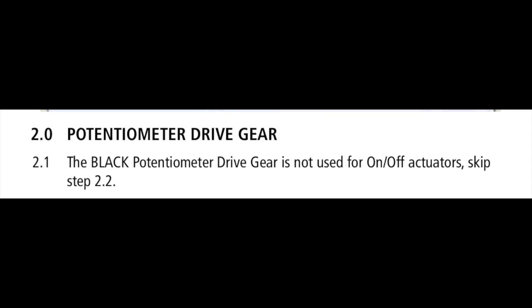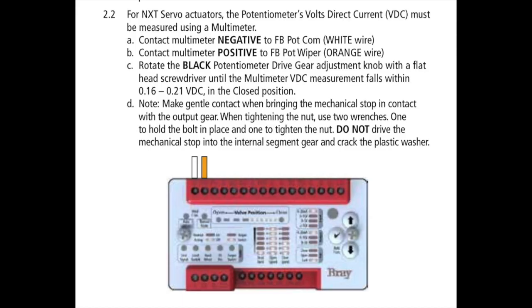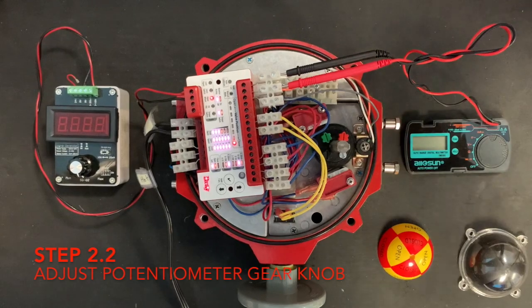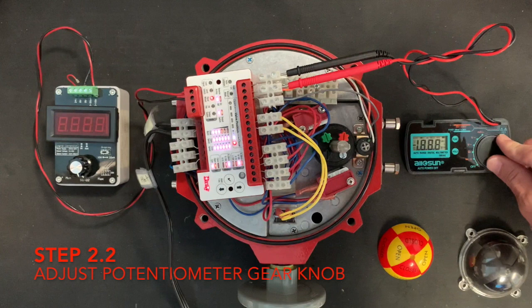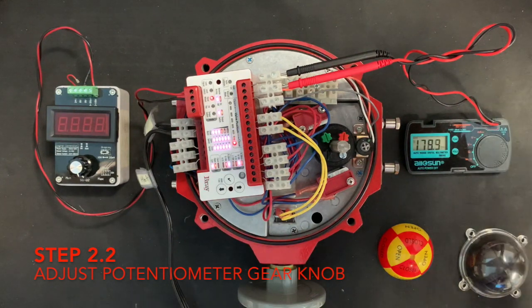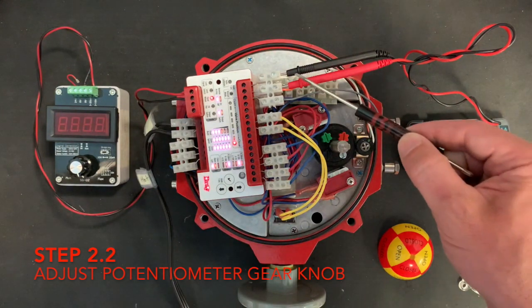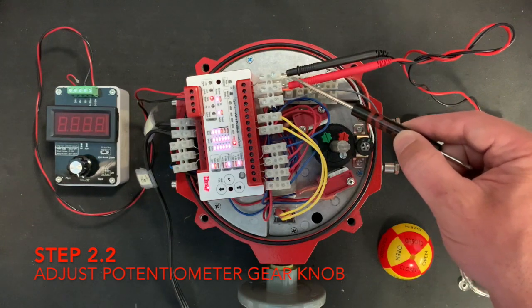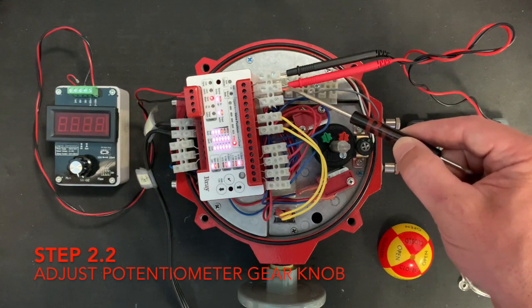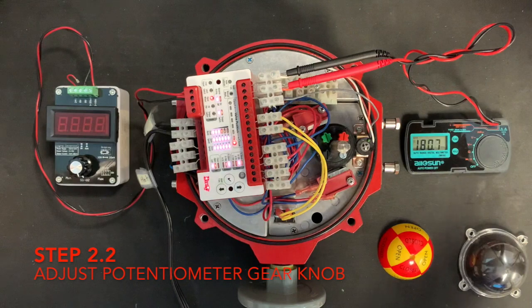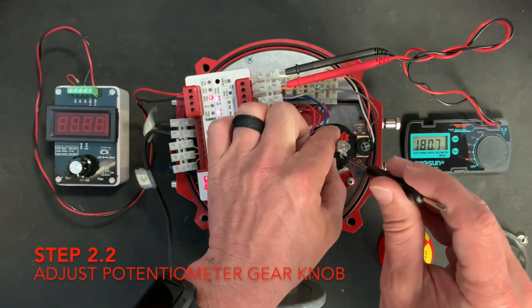The black potentiometer drive gear is not used for on-off actuators. Skip step 2.2. For NXT servo actuators, the potentiometer's volts direct current must be measured using a multimeter. Contact multimeter negative to feedback pot, common, white wire. Contact multimeter positive to feedback pot wiper, orange wire.